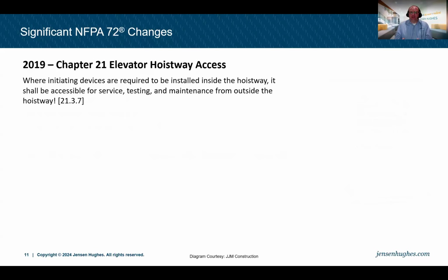Now, that also comes to our elevator hoistways. Now, elevator hoistways obviously are containing an elevator cab that's moving up and down. Occasionally, based on the codes, we have to place fire detection devices within our hoistway. Now, if that's true, as of the 2019 edition of NFPA 72, we had this requirement in 21.3.7 that if devices are inside the hoistway, they need to be accessible for service, testing, and maintenance from outside the hoistway. Now, this is done for a very, very pure reason. It's to keep our elevator inspectors safe. Not only the elevator inspectors, but the fire alarm technicians and inspectors that are working on that interface equipment.